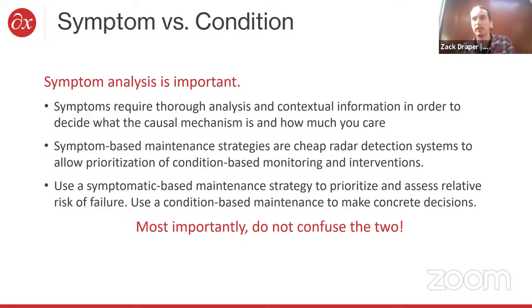It's really important not to confuse those two systems. You don't want to use dissolved gas analysis as your primary mechanism for determining serviceability in a transformer, because it's a symptom of the problem, not a condition of the transformer.